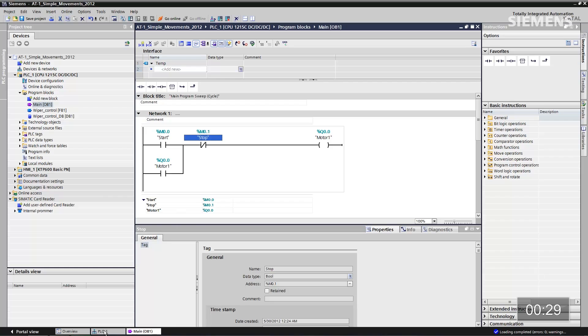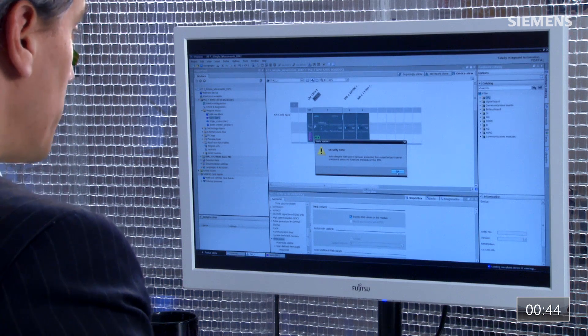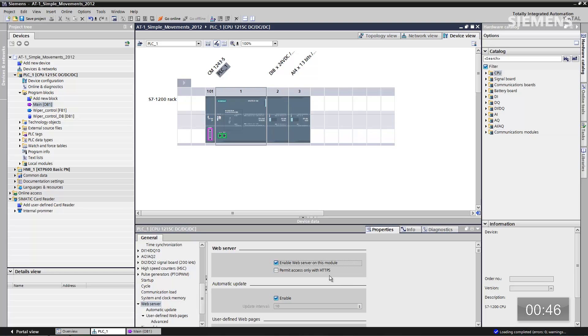Now our code is done. The next step is the web server. Go down to the controller itself, and in the property section of this 1215C you'll see the web server enable checkbox. Check that box — a quick security note pops up telling us we're enabling a web server and asking if we want additional security. We don't for this particular instance, so click OK. One thing to do is click on 'permit access only with HTTPS,' so we make it more difficult for somebody to sniff out the connection from the smart device to the control system.